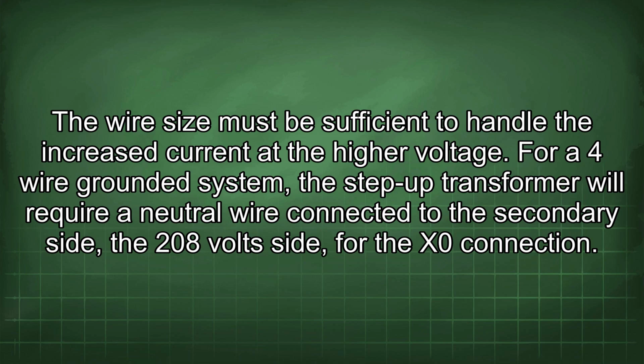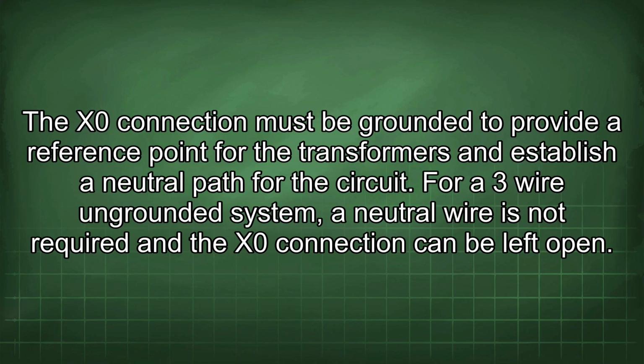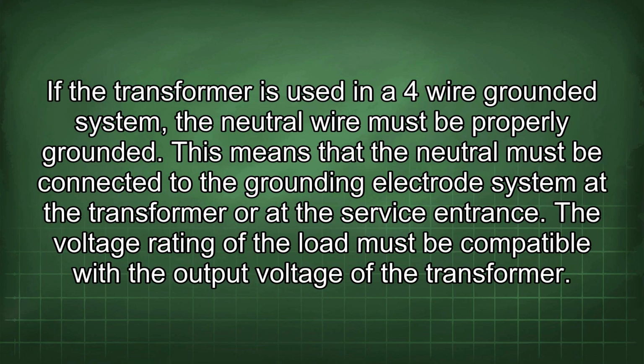For a 4-wire grounded system, the step-up transformer will require a neutral wire connected to the secondary side, the 208 volt side, for the X0 connection. The X0 connection must be grounded to provide a reference point for the transformers and establish a neutral path for the circuit. For a 3-wire ungrounded system, a neutral wire is not required and the X0 connection can be left open. If the transformer is used in a 4-wire grounded system, the neutral wire must be properly grounded.